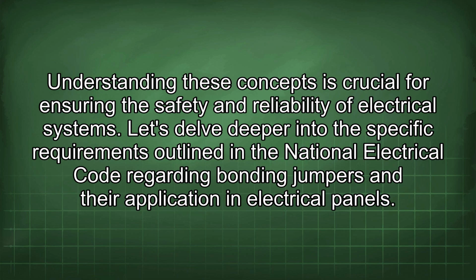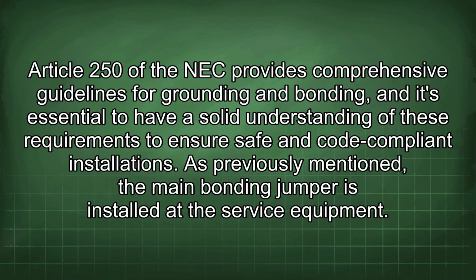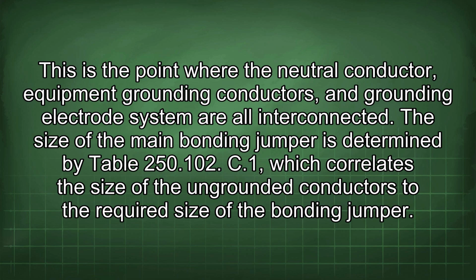Let's delve deeper into the specific requirements outlined in the National Electrical Code regarding bonding jumpers and their application in electrical panels. Article 250 of the NEC provides comprehensive guidelines for grounding and bonding, and it's essential to have a solid understanding of these requirements to ensure safe and code-compliant installations. As previously mentioned, the main bonding jumper is installed at the service equipment. This is the point where the neutral conductor, equipment grounding conductors, and grounding electrode system are all interconnected.